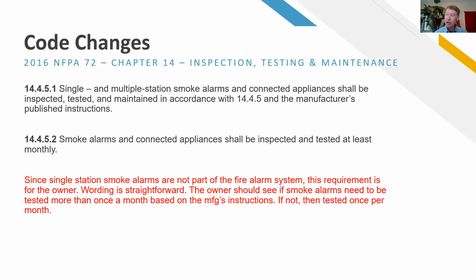Now here's one I want to clarify. There are two different kinds of detectors out there for smoke. There are single station smoke alarms - these are your 120 hardwired systems. You see a lot of them in apartment buildings or similar occupancies. They're standalone, they don't report to the fire alarm system, they won't roll the fire trucks, and they don't activate the horn strobes out in the corridor. Those are single station smoke alarms.